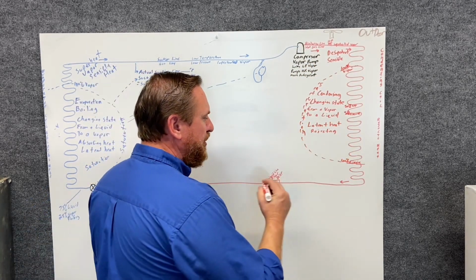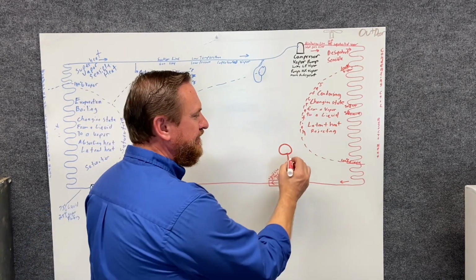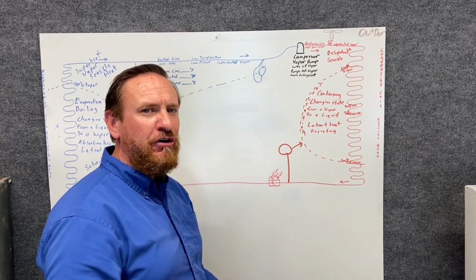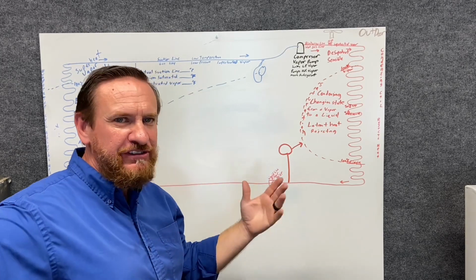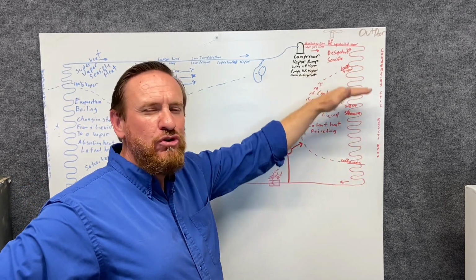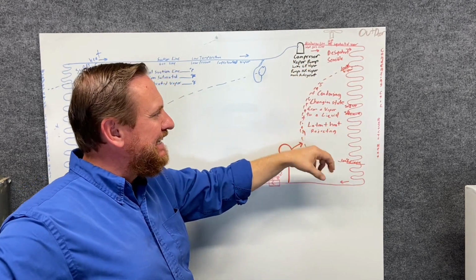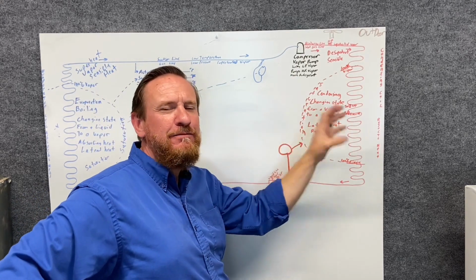We're going to hook our pressure gauge up, and that pressure is going to convert to a saturated temperature, or in this case, a condensing temperature, which is still saturation. So whatever temperature this converts to is the temperature of the majority of that outdoor condensing coil. So it's changing state from vapor to liquid, latent heat, rejecting heat, massive amounts of BTUs coming out at this point.